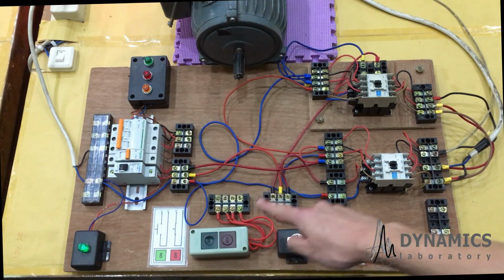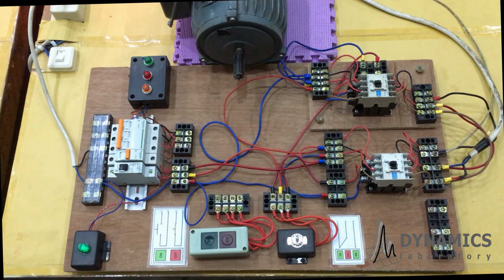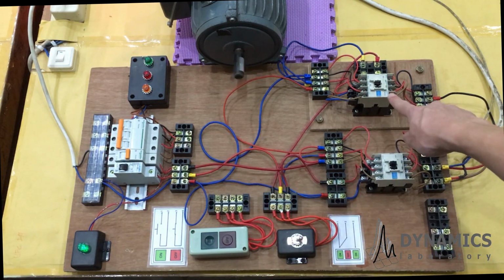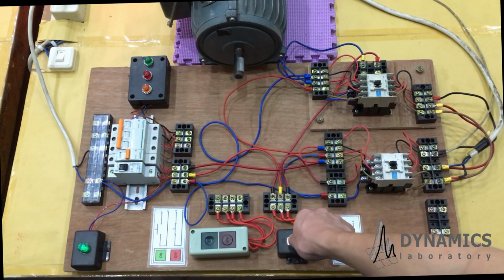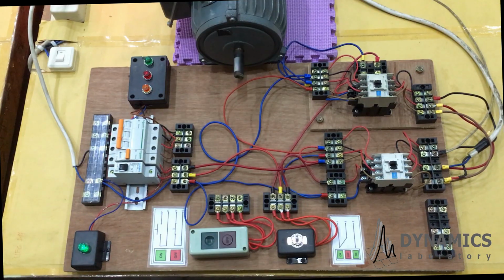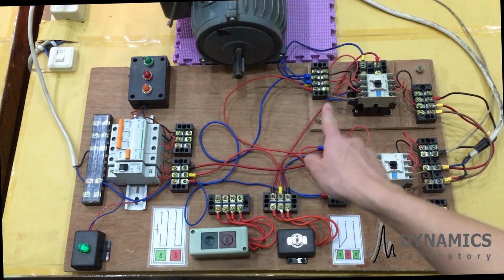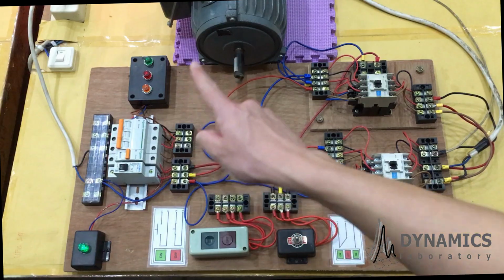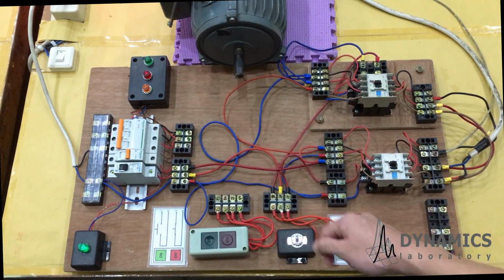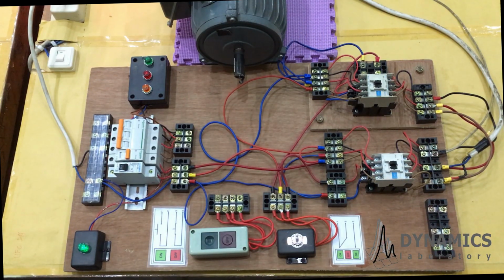Lever left position and contactor 1 is on, counterclockwise. Meanwhile, in here, right position, contactor 2 on, and the AC motor is clockwise. That's how we reverse the rotational direction of one-phase AC motor.